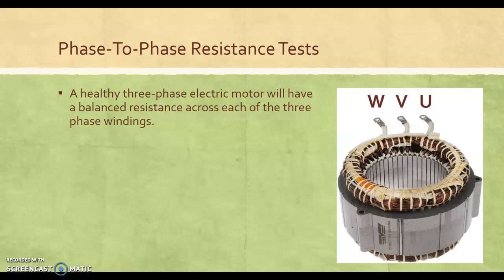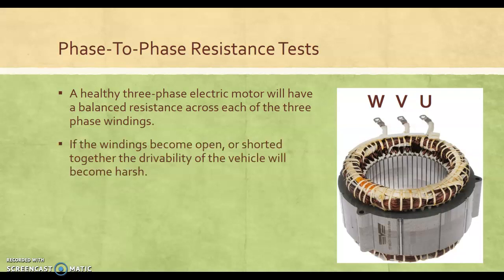But in general, until then, phase to phase is basically checking that all three of these phases, remember the Y-wound stator, are balanced. You don't want to be open, shorted, high resistance, low resistance. All that can create an imbalance. Think about your engine: you want all the cylinders to be relatively balanced when producing power. The electric motor is the same thing.